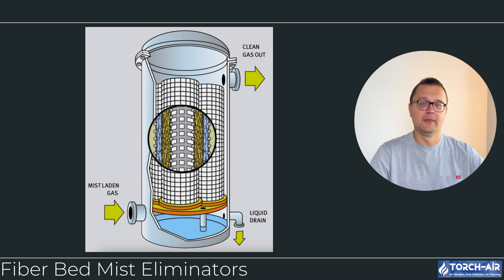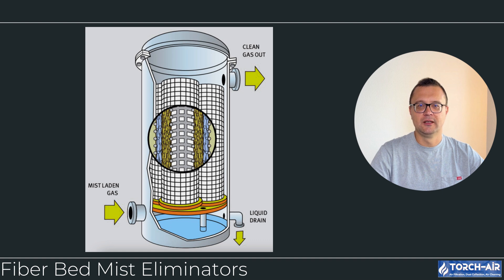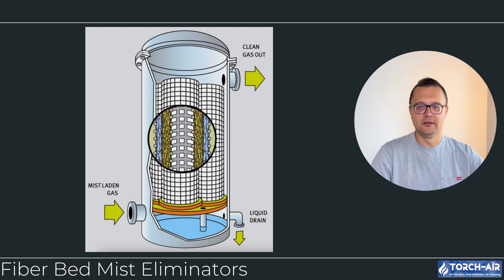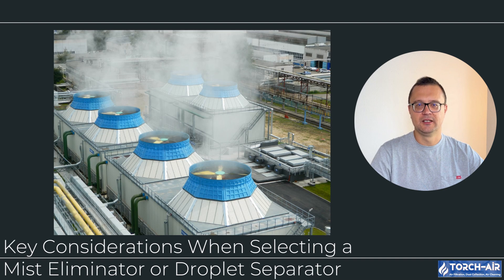Fiber bed mist eliminators, also known as candle filters, use tightly packed fibers to trap mist and aerosols as the gas stream passes through the bed. The mist droplets coalesce on the fibers and then drain down to be removed. Best for ultra-fine mist and aerosols, they are extremely efficient at removing submicron droplets, making them ideal for applications like sulfuric acid production or chemical processing. However, they require more maintenance and may need frequent cleaning or replacement depending on the dust or particle load.